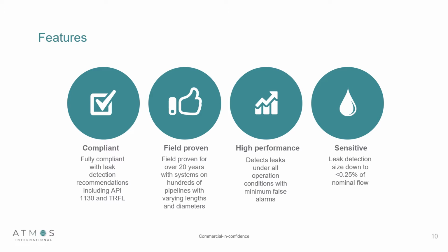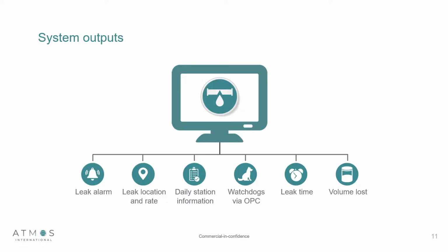It's been field proven for well over 20 years on hundreds of installations of varying pipeline lengths, varying diameters and varying complexities. So we can do multiple inlets, multiple outlets, short pipelines, single in and outs, oil, gas, multi-product. It can detect leaks under all operational conditions with minimal false alarms, and it has a high level of sensitivity. It provides an array of system outputs from leak alarm, leak location and rate, daily station information, watchdogs via OPC, leak time and volume lost. And all this information can be presented in a graphical user interface, and we are moving into a new HMI as well.